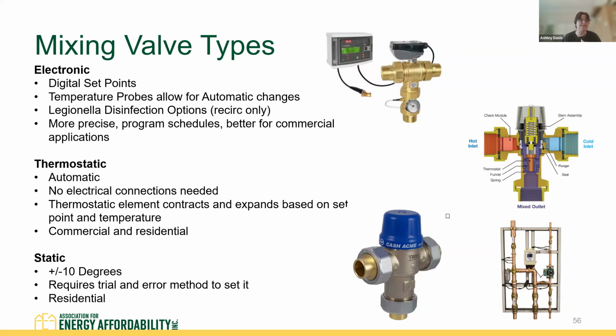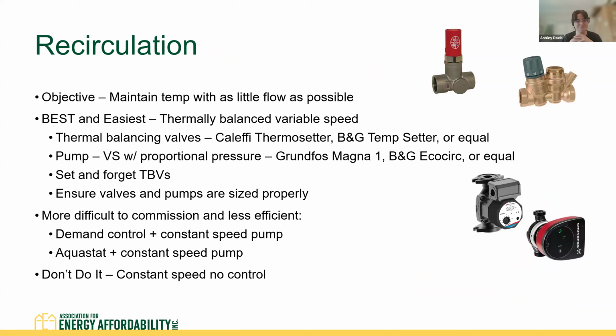And then static mixing valves, typically wouldn't recommend these for a central plant because they don't adjust based on the hot and cold temperatures, right? You just kind of set them to a certain ratio and leave them alone, which means they can require a lot of trial and error and are much less precise. They can't really deliver like a continuous temperature. Next slide. And then choosing a recirculation control strategy is important as well, right?